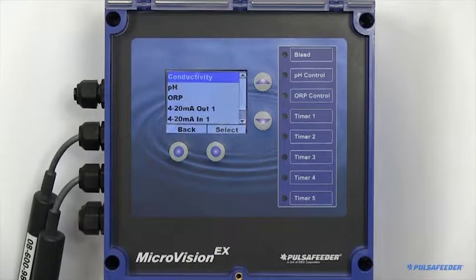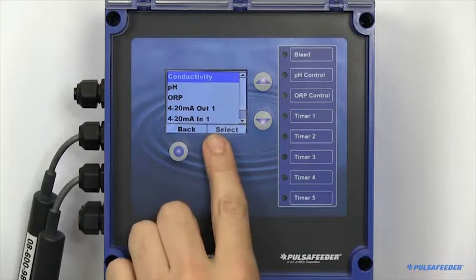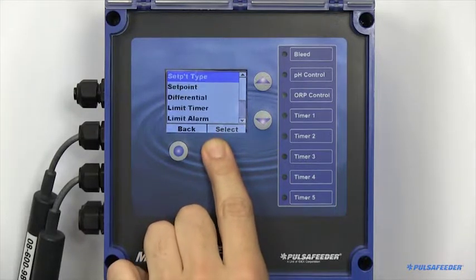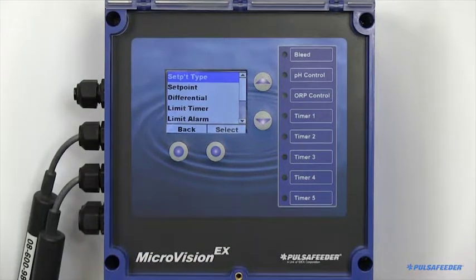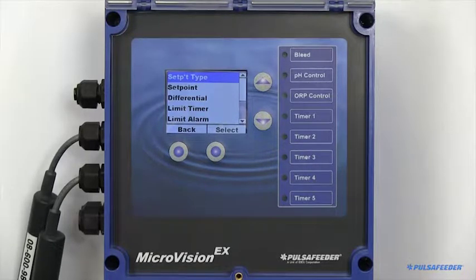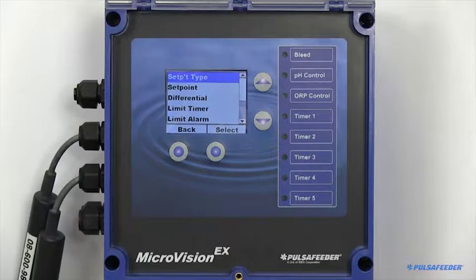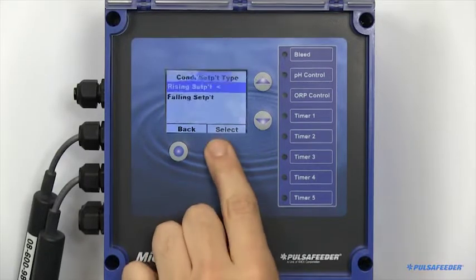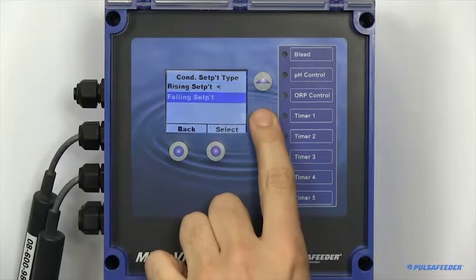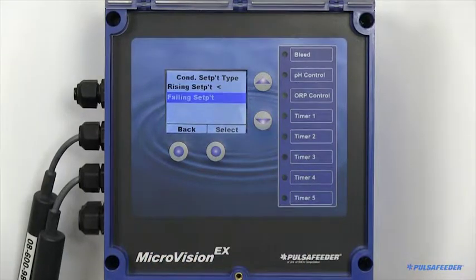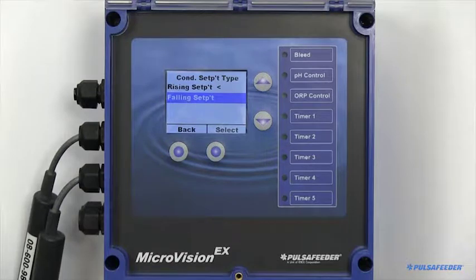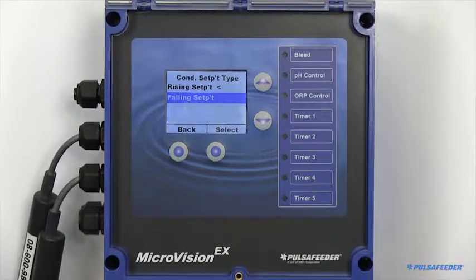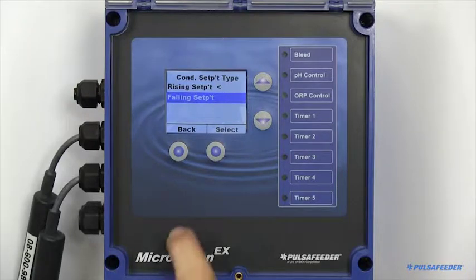All probe types are configured the same way. This is an example of how to set up your conductivity probe. The pH and ORP probes will be done identically. To set up your conductivity probe, you need to choose your set point type. You can choose between rising or falling. Rising type means that the output activates when the input goes above the set point. Falling type activates the output when the value goes below the set point.